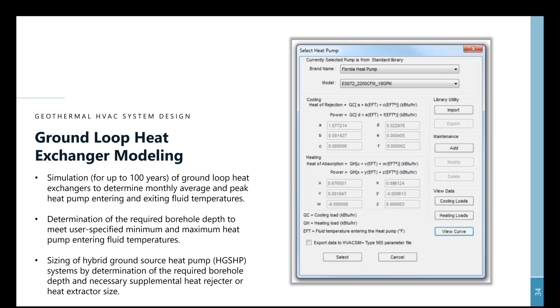In the event that you have a very imbalanced load, so let's say you have 10-to-1 cooling versus heating loads in your building, the software can also size what we refer to as a hybrid ground source heat pump system, which is basically determining, if I need supplemental heat rejection, how big that heat rejection needs to be to keep the bore field in balance. So the modeling system can assist you with that as well.